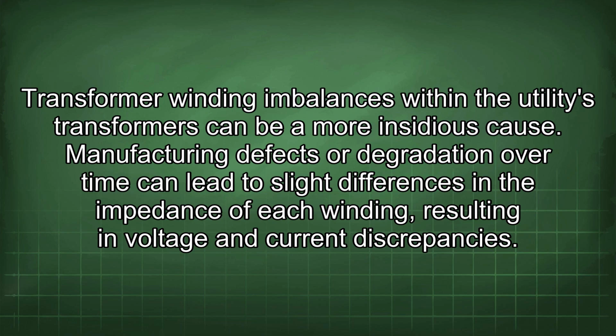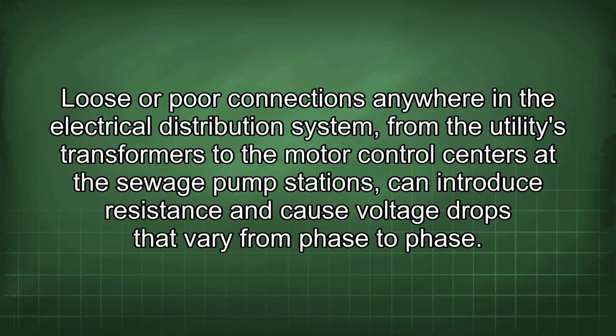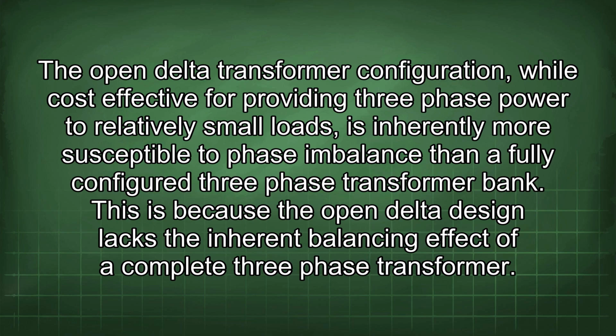Loose or poor connections anywhere in the electrical distribution system, from the utility's transformers to the motor control centers at the sewage pump stations, can introduce resistance and cause voltage drops that vary from phase to phase. The open delta transformer configuration, while cost-effective for providing three-phase power to relatively small loads, is inherently more susceptible to phase imbalance than a fully configured three-phase transformer bank. This is because the open delta design lacks the inherent balancing effect of a complete three-phase transformer.